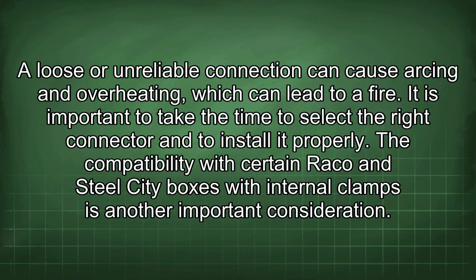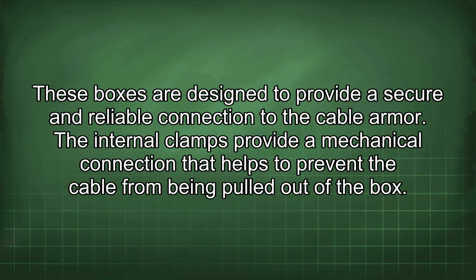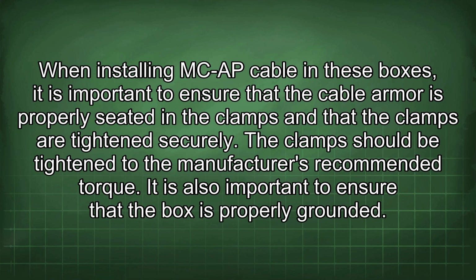The compatibility with certain Raco and Steel City boxes with internal clamps is another important consideration. These boxes are designed to provide a secure and reliable connection to the cable armor. The internal clamps provide a mechanical connection that helps to prevent the cable from being pulled out of the box. When installing MCAP cable in these boxes, it is important to ensure that the cable armor is properly seated in the clamps and that the clamps are tightened securely.